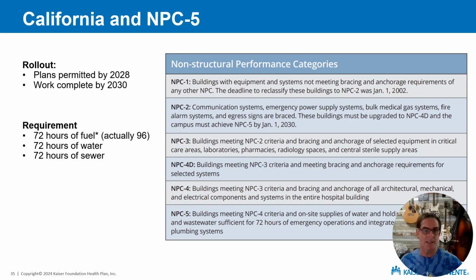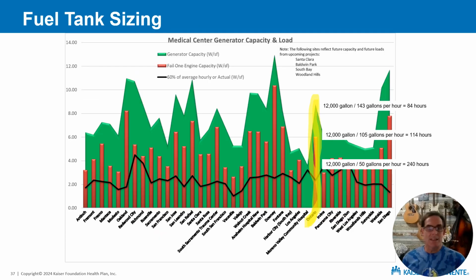These requirements were put into the code in the late 80s and the early 1990s based on some earthquake activity in California. And the way that code is written, we have to store fuel sufficient to run their generators at their nameplate capacity for 96 hours. And then we have to provide on-site water storage based on this number, 50 gallons per bed per day for 72 hours. So what does that mean? That actually means that our fuel tanks are going to get way oversized. So just to look at an example here, this is our Ontario hospital in Southern California. Currently we have a 12,000 gallon fuel tank, which based on the nameplate of the generators can only get us 84 hours of runtime. So we need to upsize this tank to provide 96 hours of runtime at the nameplate of the generator. But we're never going to be able to put that much load on the generator.